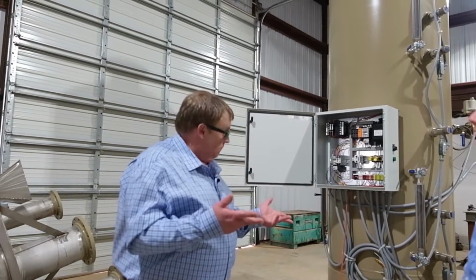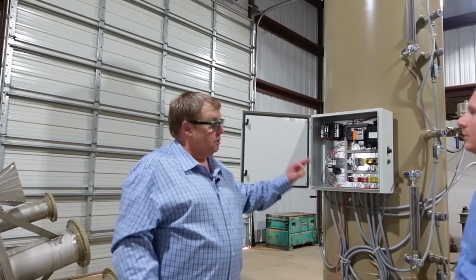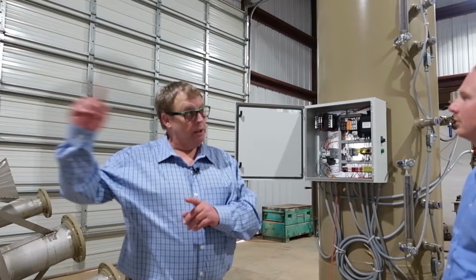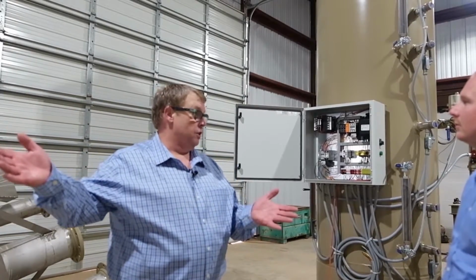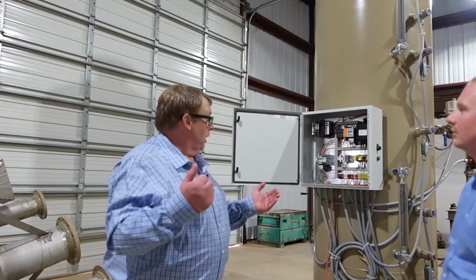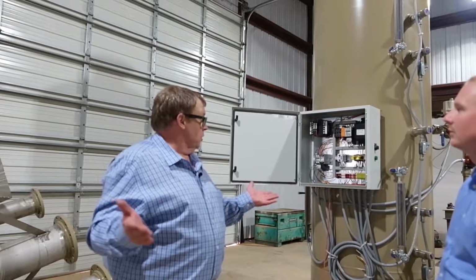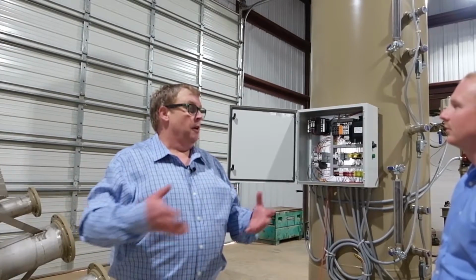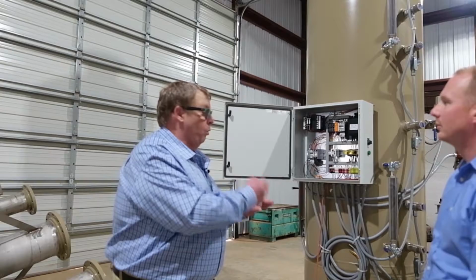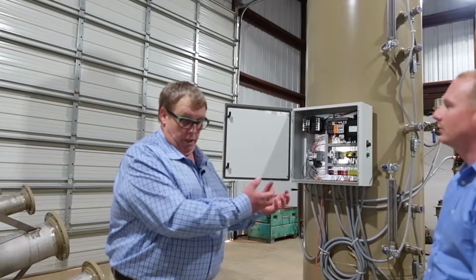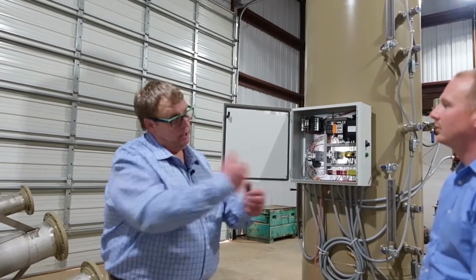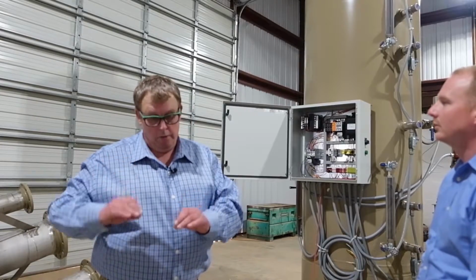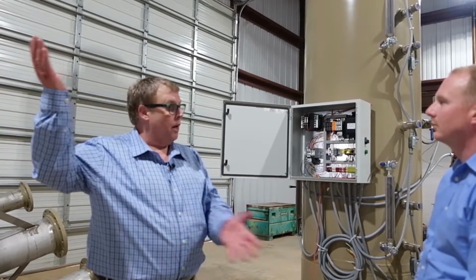And then finally, we can use the secondary output to send a signal to their SCADA, whichever way they're used to collecting it. I know our two main customers, which are Cimarex and Apache, both of those companies use a total flow, and they take the output from the Moore as an input to the total flow, and from there that will upload to their SCADA so that they can keep good documentation.